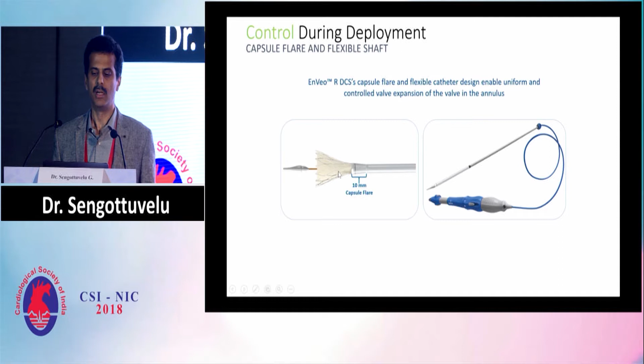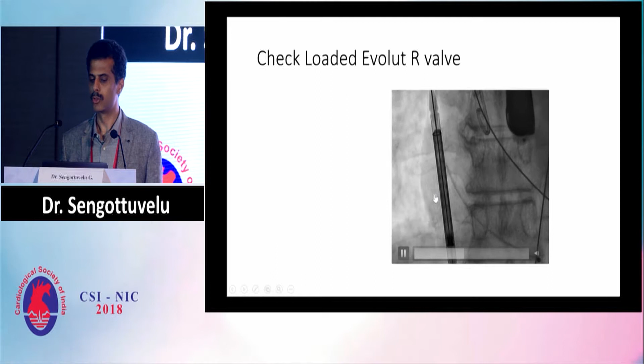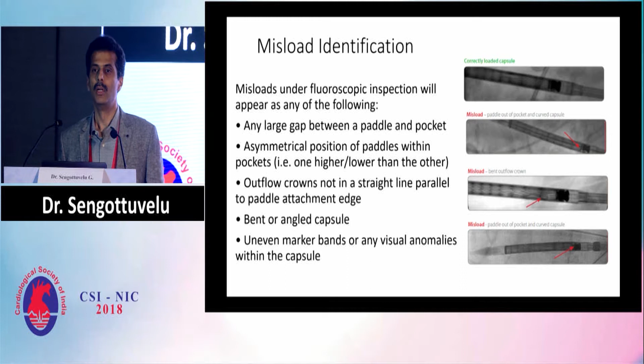Initially, as the valve is loaded, it is very important, even before doing a balloon valvotomy, to check whether the valve is loaded properly. So a cine fluoroscopy recording is done, and the valve is rotated to look for any misload. Particularly look at the paddle and make sure there is no large gap between the paddle and the pocket. This is the correctly loaded valve capsule, and here there is a large gap. The paddle is out of the pocket. Also, the outflow crowns should be parallel to each other, and any loss of parallelism again indicates misload. You also have to look for any uneven marker bands or any visual anomalies within the capsule. So it is very important to make sure the valve is loaded well before we start doing the BAV.